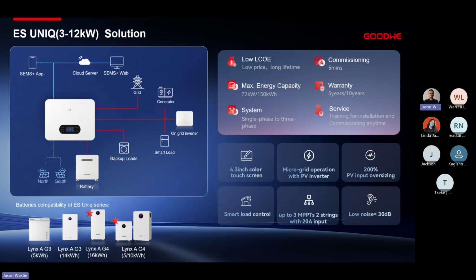An extremely unique feature for our inverters is the 200% PV input oversizing. This is usable oversizing, meaning for the 12 kilowatt ES UNIQ, for example, we can connect 24 kilowatts of PV on it, and all 24 kilowatts is usable. At the same time we can run 12 kilowatts of power to our loads and 12 kilowatts of power can charge our batteries. So in the early morning, if we've got a heavy load and the batteries are quite low, we'll be able to disperse more than 12 kilowatts worth of power between the inverter, batteries, and the loads.